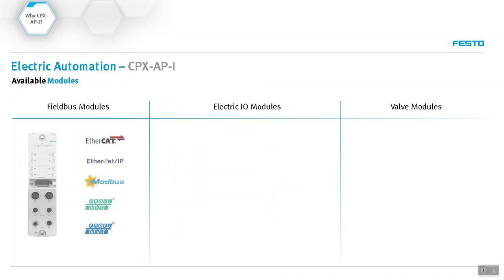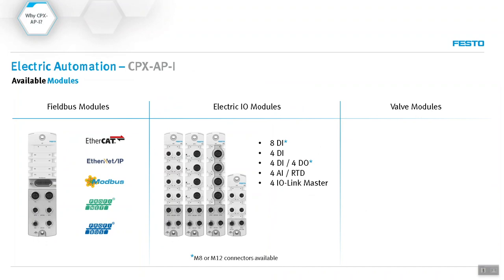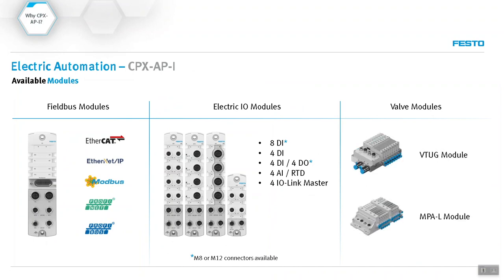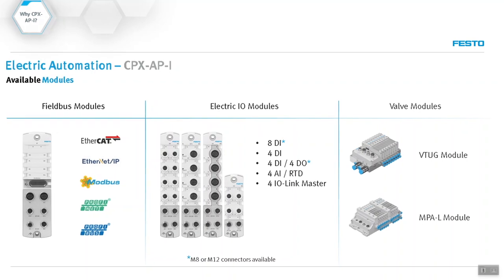Now in terms of which modules do we have, on the left-hand side you can see the different fieldbuses that we support. In the middle there we have digital input and output modules, analog modules for 4 to 20 milliamps, 0 to 10 volts, RTD signals, and also the IOLink master with four channels. The nice thing is that we also support valve manifolds. Everything falls under the same communication protocol.